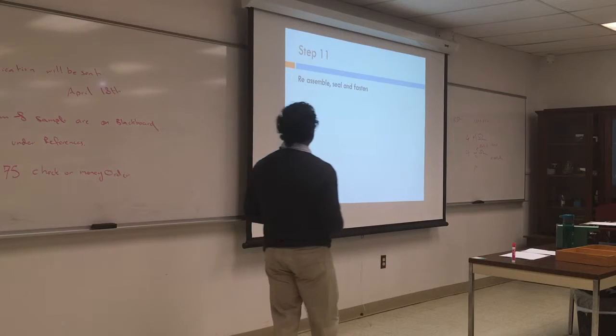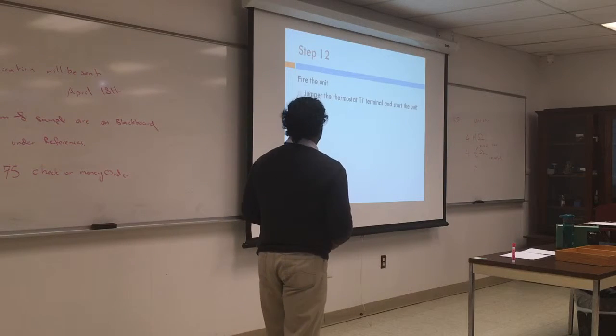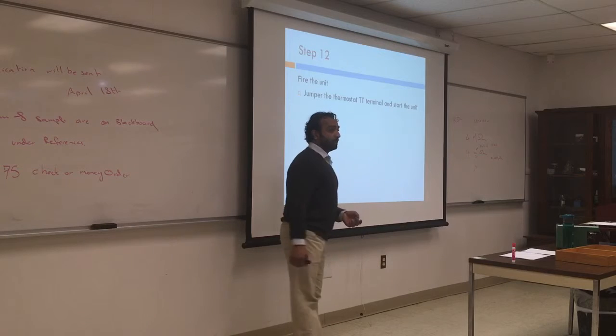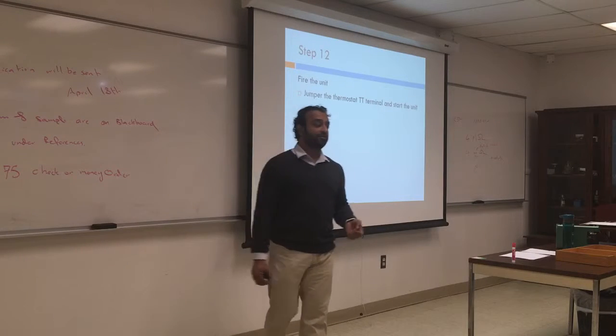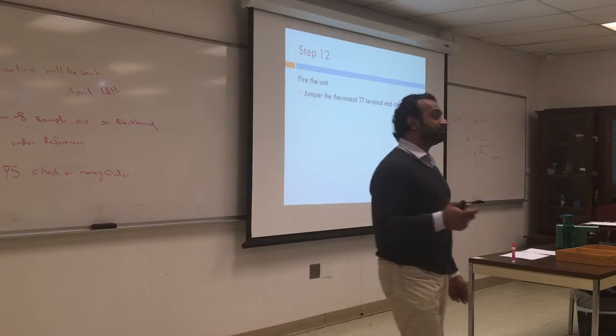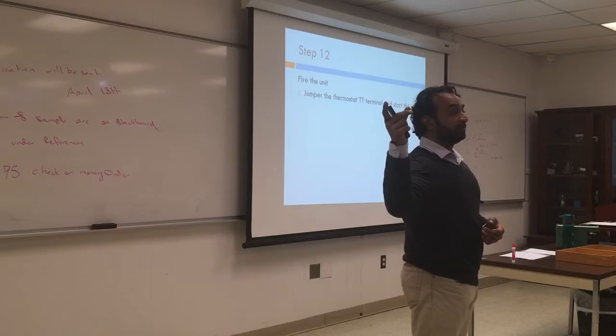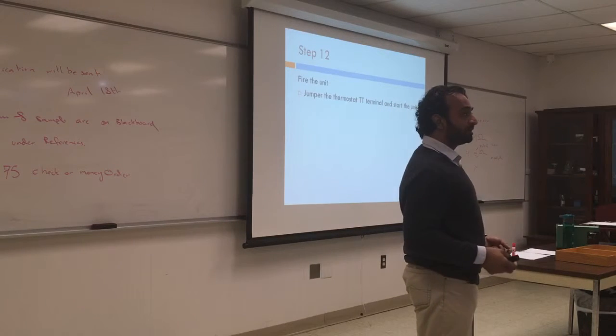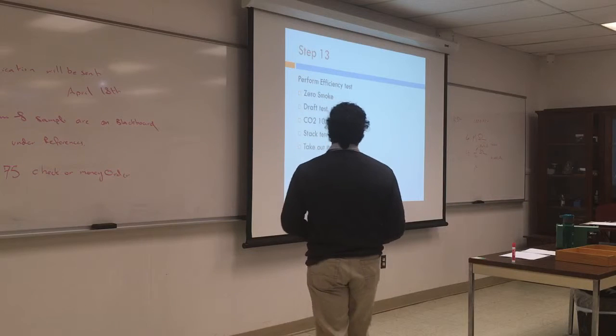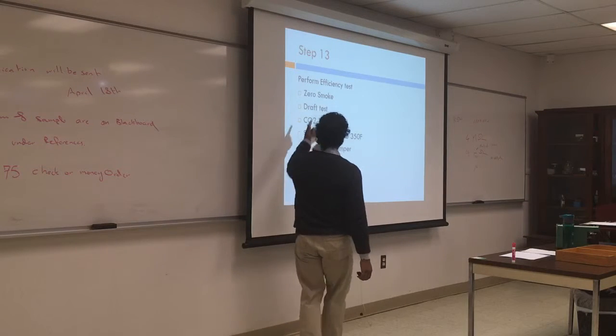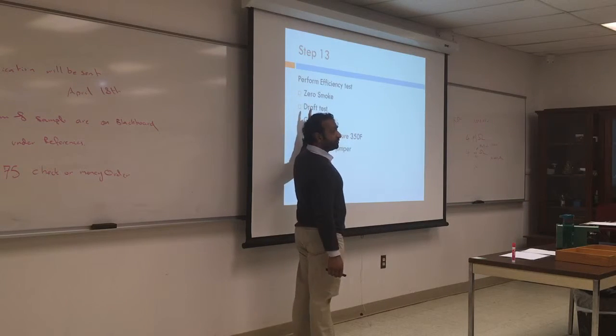Reassemble, seal, and fasten. Fire the unit. So again, the unit probably has a thermostat inside the house, so it's not really convenient to go up and turn on the thermostat, so you can just jump the thermostat and see it work. Check, we'll do an efficiency test, we'll go through the procedure.